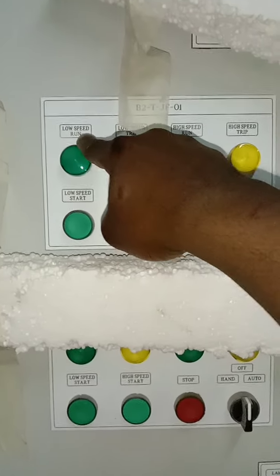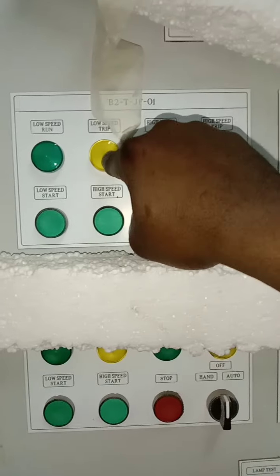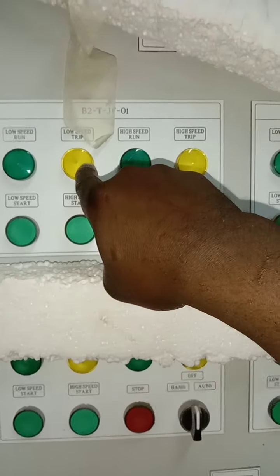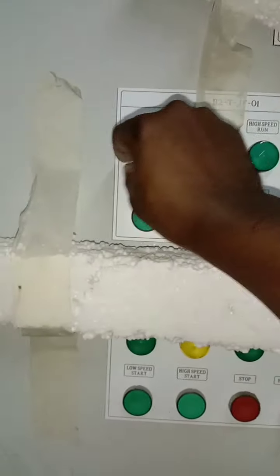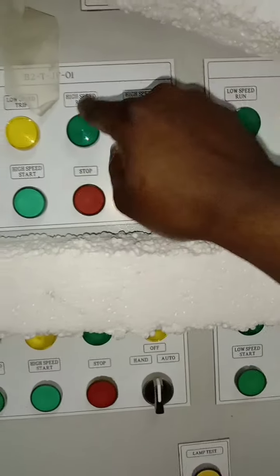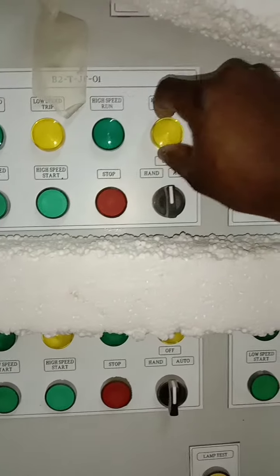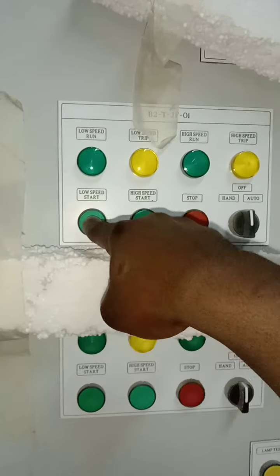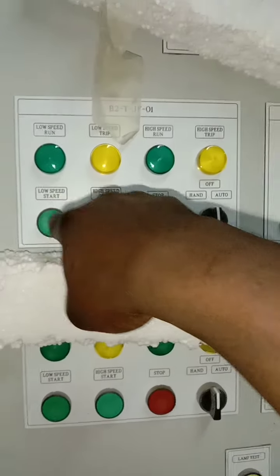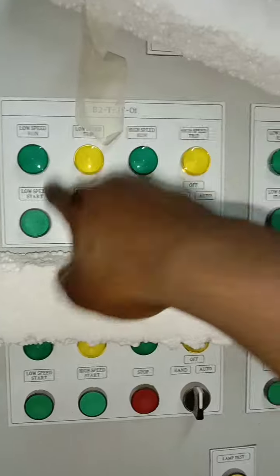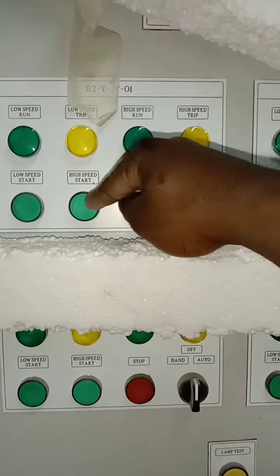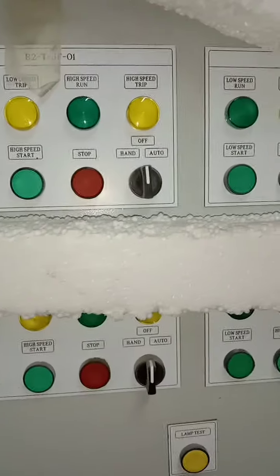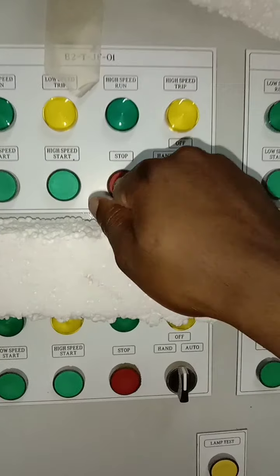This indicates the fan is running on low speed. This indicates the fan that is running on low speed has tripped once you see this light on. And then on the other side is the high side of the fan. Below it's low speed start. This is when you start this fan at low speed, and then this other part you start this fan at high speed. And then here is a stop push button when you want to stop the jet fan.